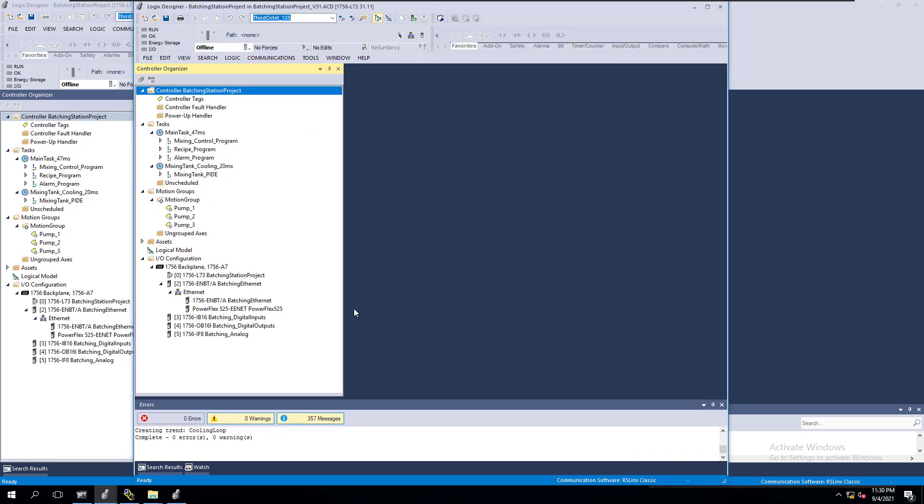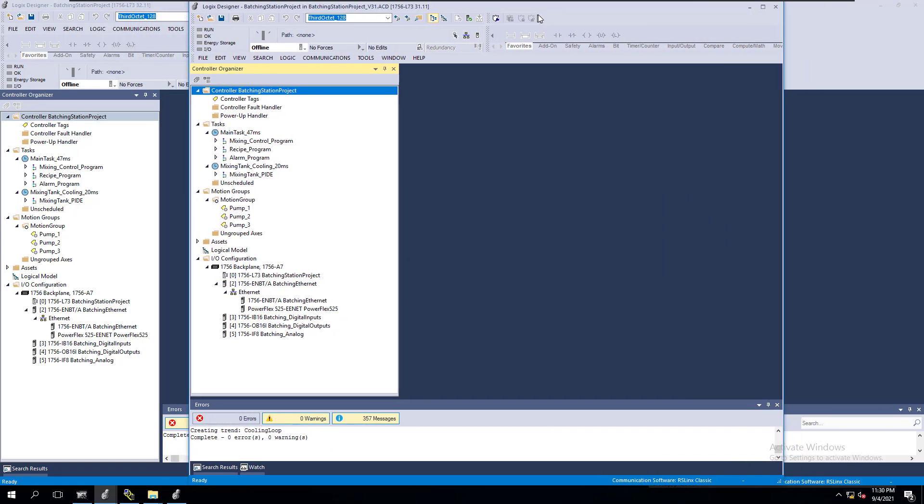So all you had to do was edit the L5K just a little bit. But I will tell you again, you're going to have to edit that L5K file. Now you can do that in Notepad Plus Plus, or you can do that in standard Notepad. But again, you just edit it as the error message comes up. If it fails for a different version or a different reason, it may be because of your actual AOIs. If you have custom AOIs that are built in your system, then you will run into a different problem that you need to fix, and that is the AOI. So that revolves around fixing the AOI.